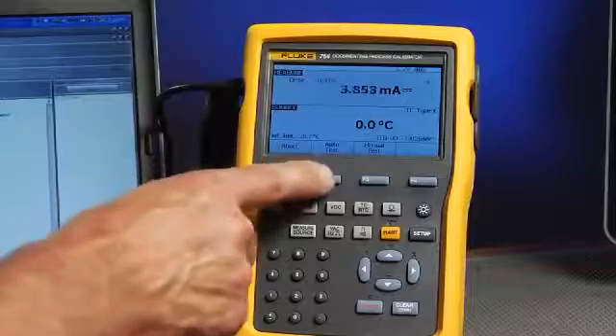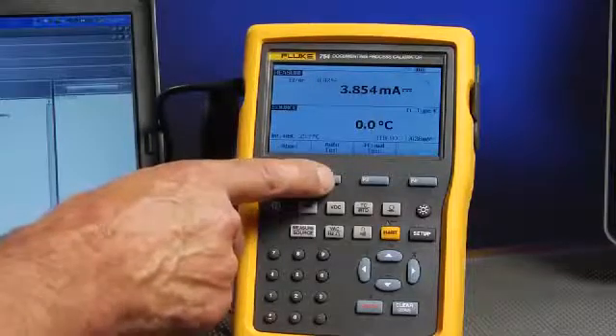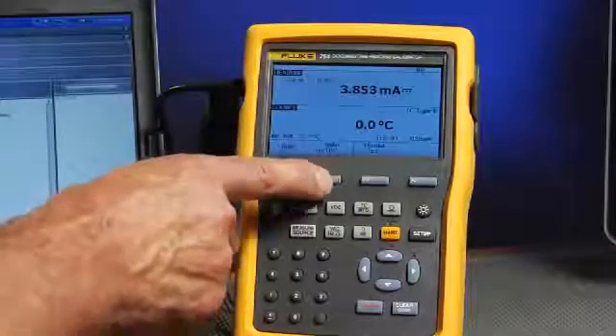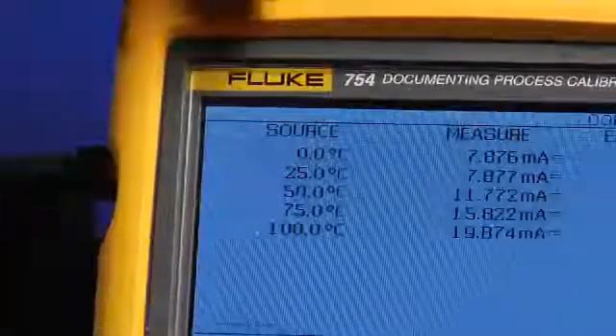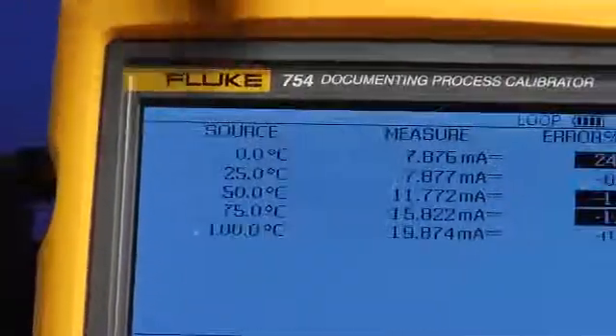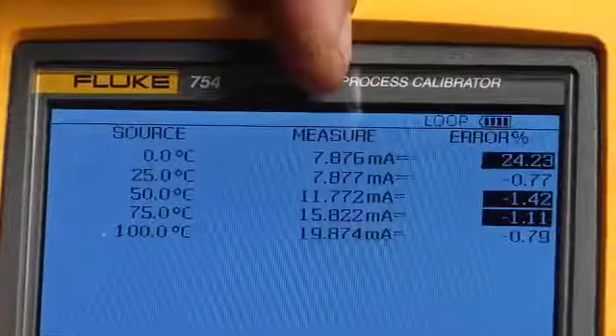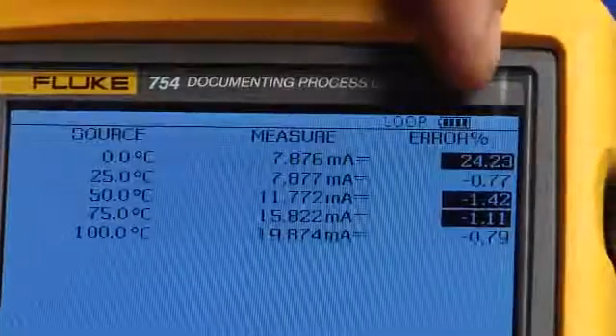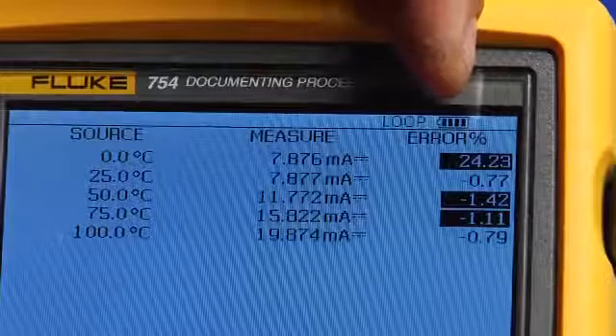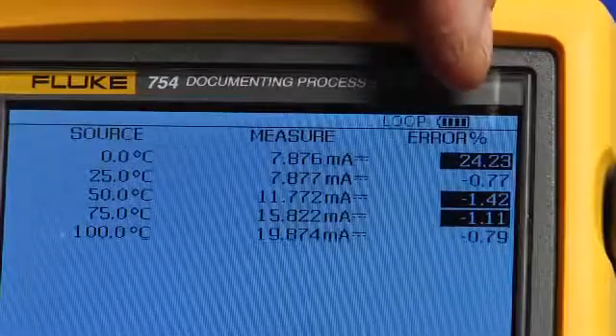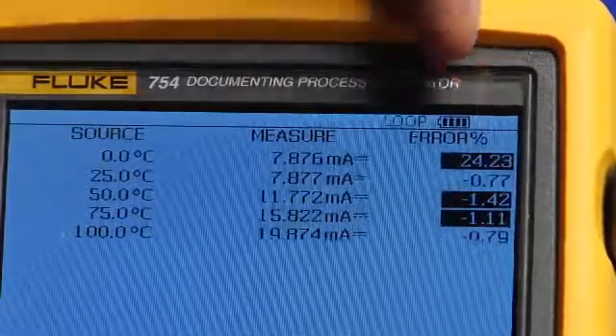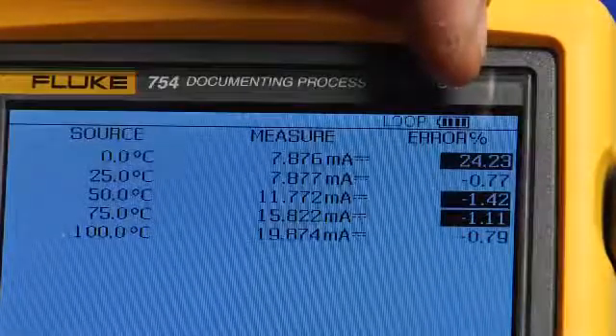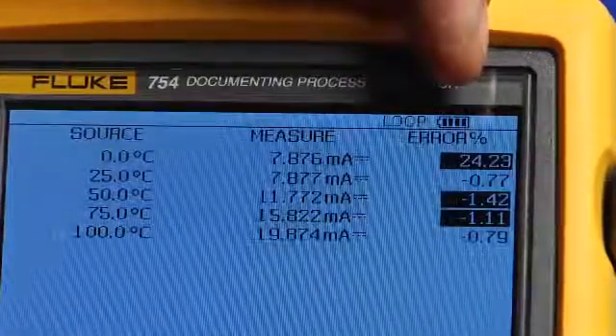Then select auto-test to automatically document the performance of the transmitter. So here you see the recorded temperature values that were applied, milliamp values that were measured, and the errors percent of span. If the error percent of span is found greater than the test tolerance, it's flagged in reverse video. In this case, this indicates that this as-found test of this transmitter has failed.